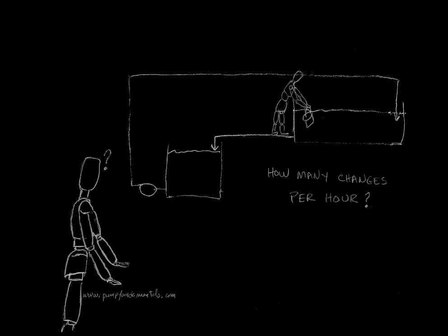At this point, we need to establish a flow rate. I'm going to consider that the total volume of the display tank has to be replaced once per hour. That sounds reasonable to me for my fictitious fish, but I would check that with an aquarium specialist. Their experience would be very useful. If this were an industrial system, the criteria would be different. You may need to supply some equipment downstream that requires a certain flow rate to meet production goals.